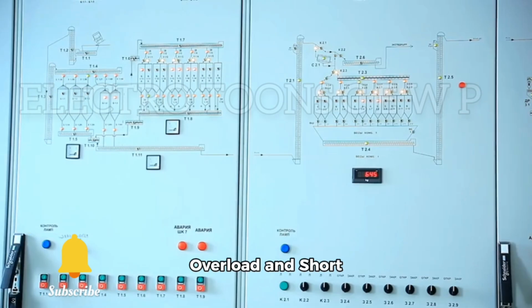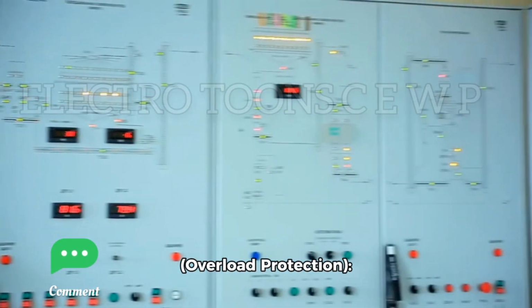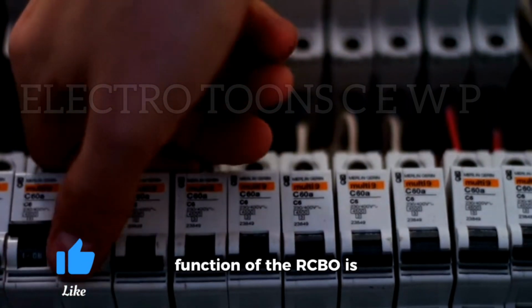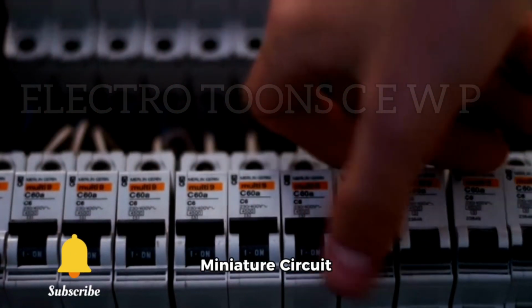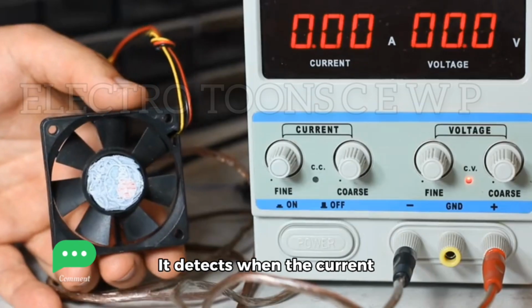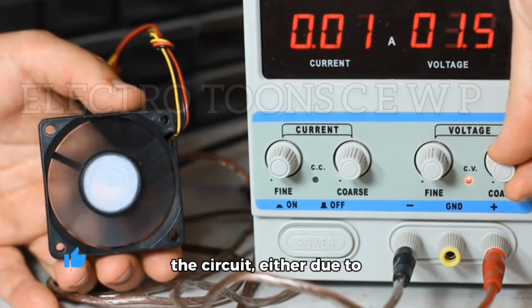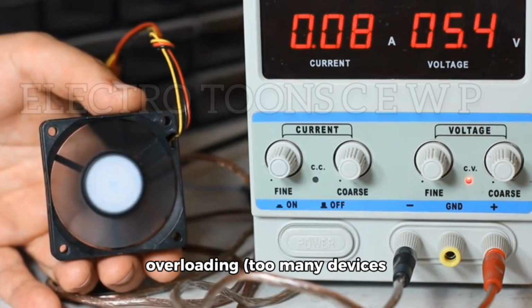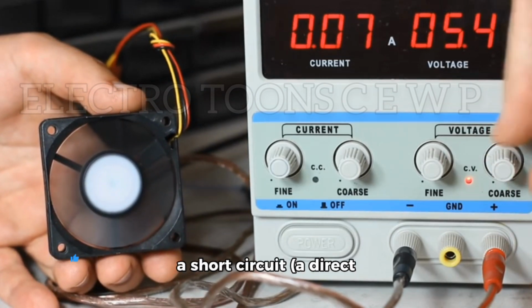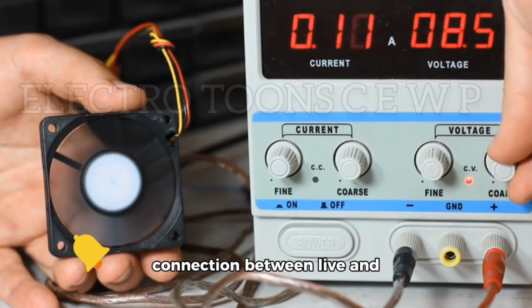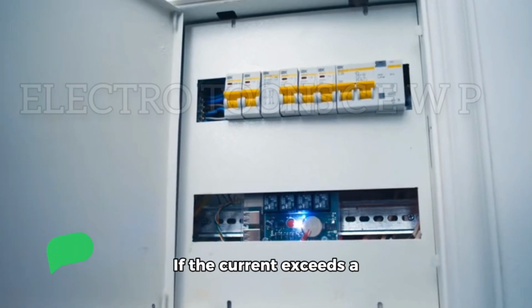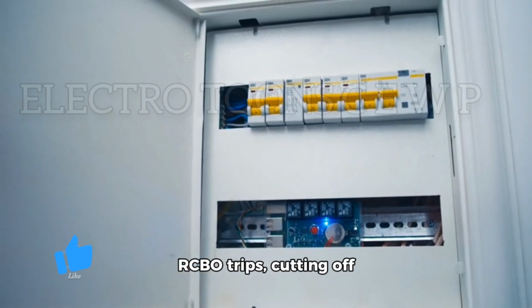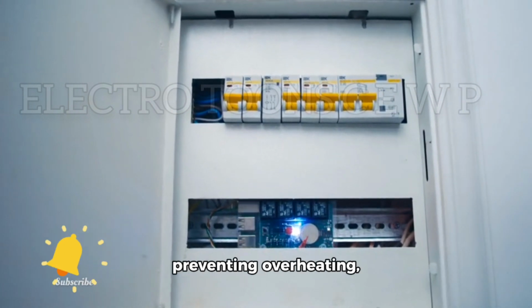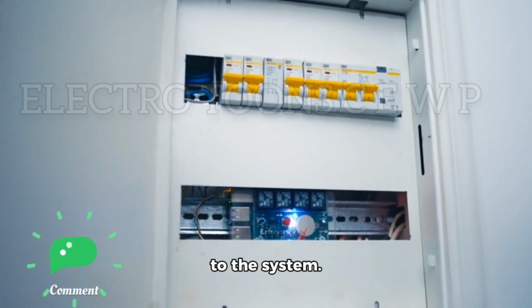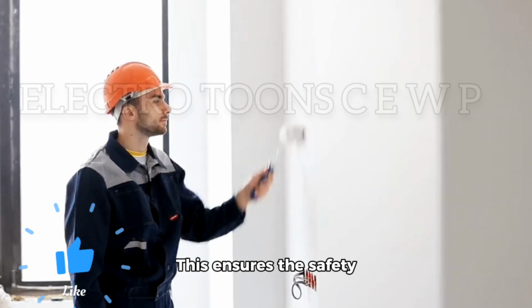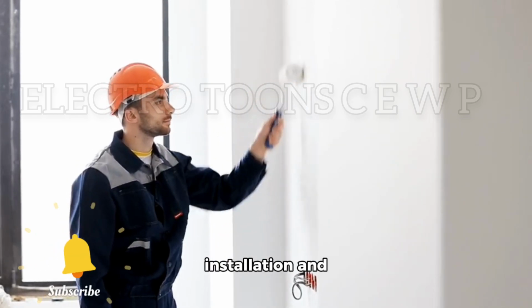Overload and short circuit detection. Overload protection. The overload protection function of the RCBO is similar to that of a miniature circuit breaker (MCB). It detects when the current exceeds the rated limit of the circuit, either due to overloading, too many devices connected to the circuit, or a short circuit, a direct connection between live and neutral wires. If the current exceeds a preset threshold, the RCBO trips, cutting off the power supply and preventing overheating, fire, and further damage to the system. This ensures the safety of both the electrical installation and connected devices.